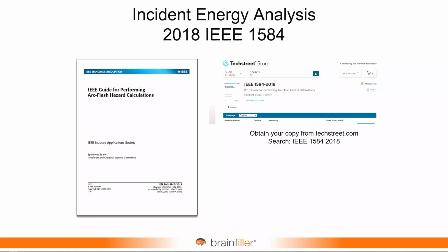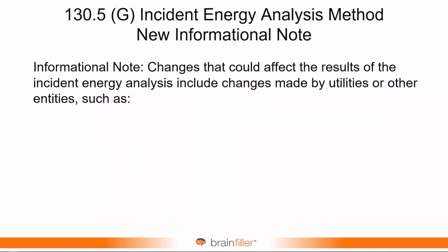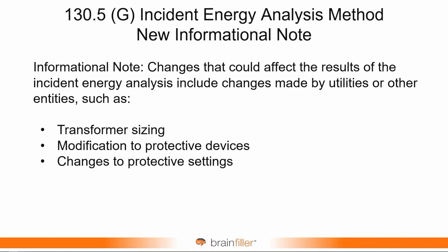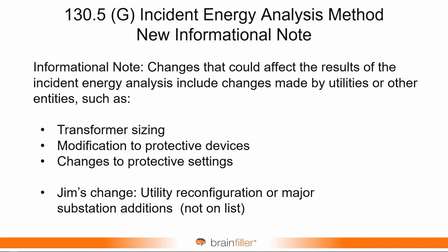Realistically, most people are going to use software, but the software uses the model from IEEE 1584. And there's a lot of data that goes into this, including the source data, the short circuit data. So if there are changes that could cause major changes within the study, those need to be addressed. So the new informational note lists changes that could affect the results of the incident energy analysis: by the utility, transformer sizing, modification to protective devices, changes to protective devices, and then I have my change.